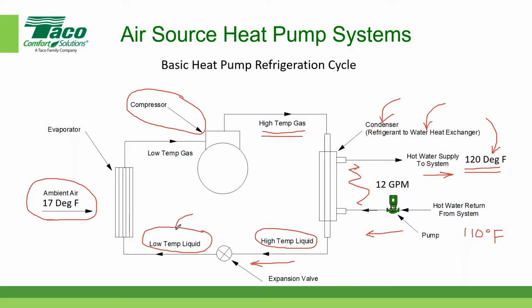So the temperature of the refrigerant at this point here has to obviously be lower than the ambient temperature in order to extract heat. And so we're just going to make up a number and say that that low temperature liquid is somewhere around 10 degrees Fahrenheit. I'll just put a number in there so you can get an idea. So that means that the low temperature liquid will evaporate, and as it evaporates, it absorbs heat from the outside air, and then it becomes a low temperature, low pressure gas that enters back into the compressor over here. So that's how we can get the refrigerant cycle to extract heat from a relatively low ambient air and generate hot water, which is sufficient enough for heating a building.